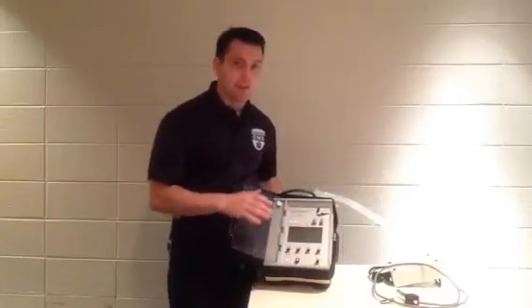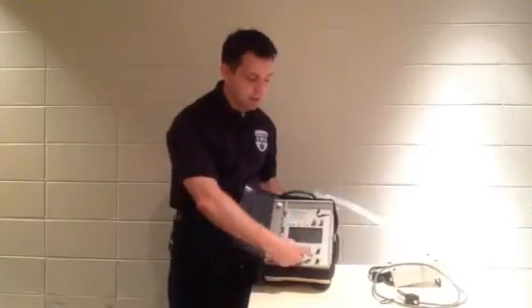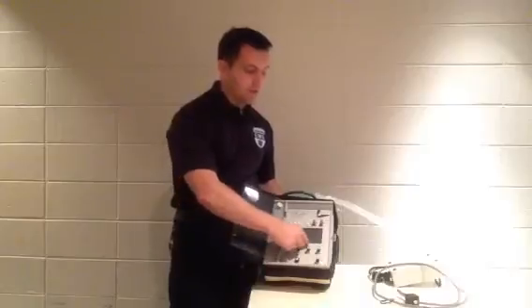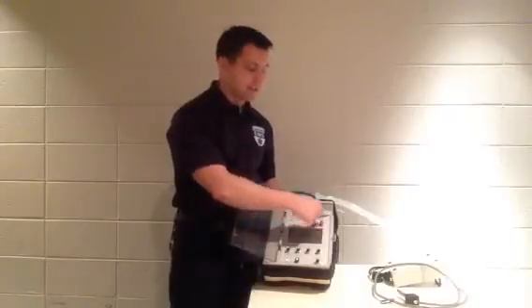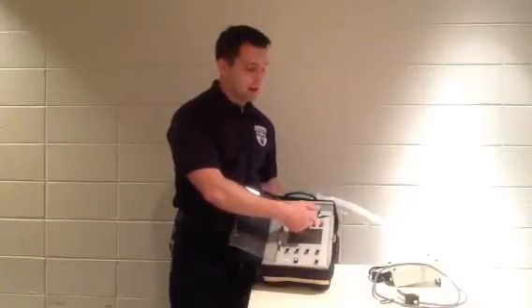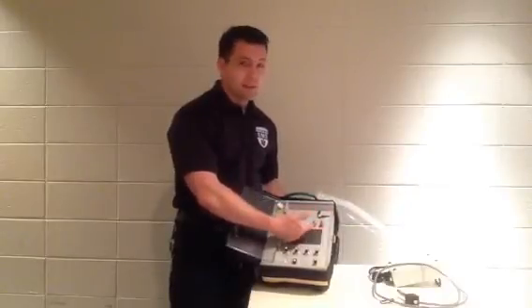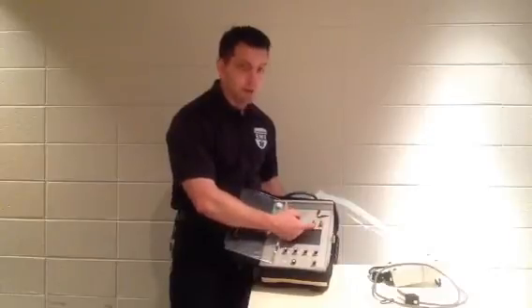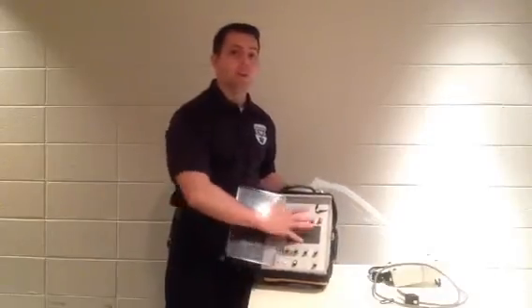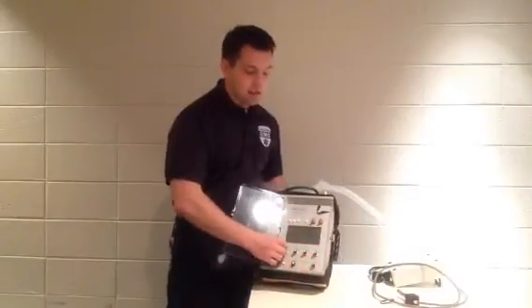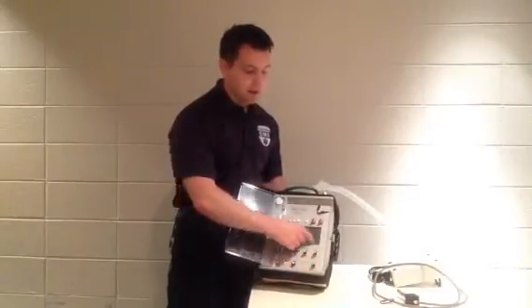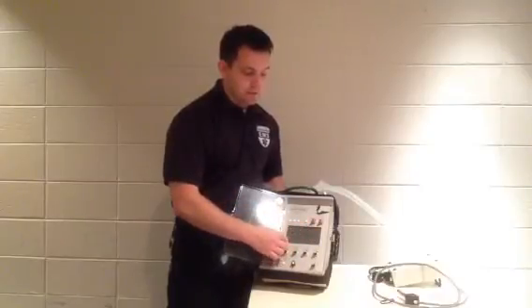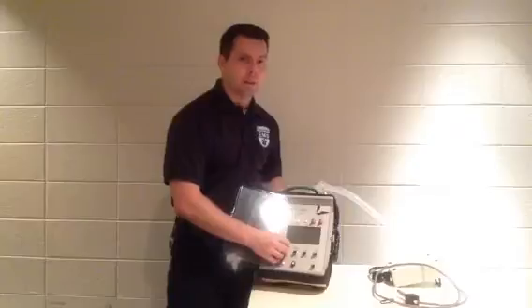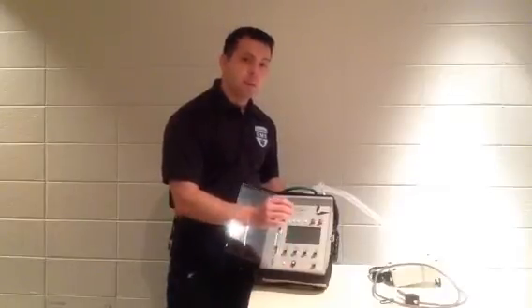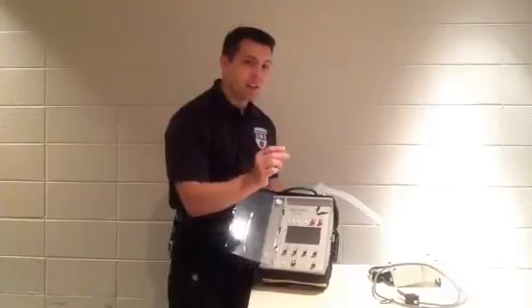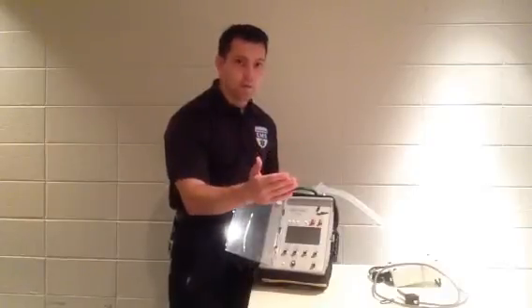One of the nice aspects is that it is very, very basic. It's literally numbered 1, 2, 3, 4, 5, and then this should say 6 and 7, but it doesn't, unfortunately. That would be a better mental cue. The nice thing is they are in red, and that's going to be your high pressure and your low pressure dial. The other downside with this particular ventilator is that these knobs, they're turn knobs. They have an electric readout right here, and these knobs are extraordinarily sensitive. You're going to go from like 12 breaths to 14 breaths, and you give it the tiniest little touch, and it shoots right up to 24.